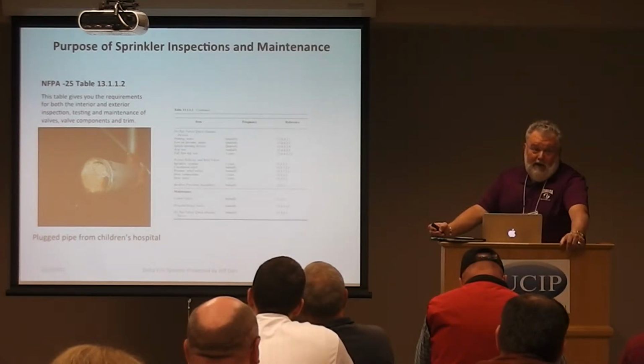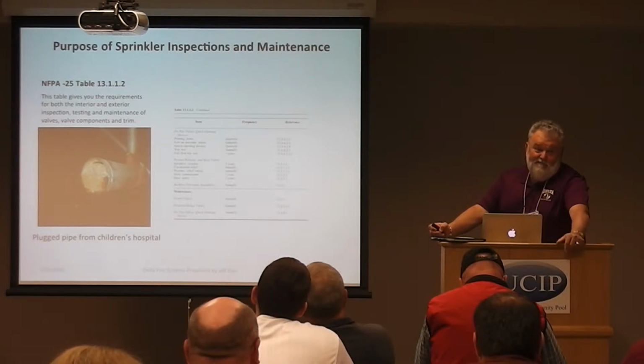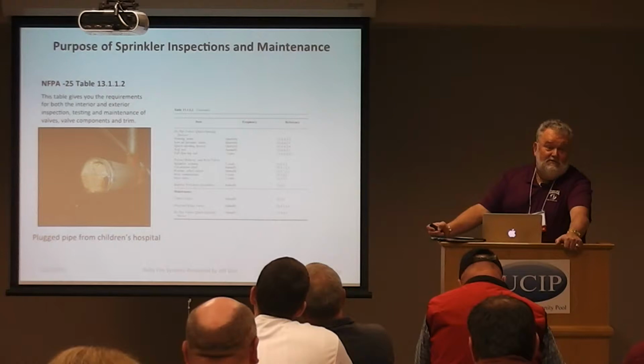The MIC problem actually is worse on that than it is on the heavier walled pipe. In addition, they've gone away from as much chlorine in water as they used to. So they're not killing that bacteria like they used to in the past, so it's still allowing it to survive. And, you know, the sprinkler system, a wet system, is totally stagnant once that system's filled up. So it's going to occur in there quite often. And we've got systems out there 50 years old that are still in great shape, and some that have been installed 5 years, we already had MIC problems.